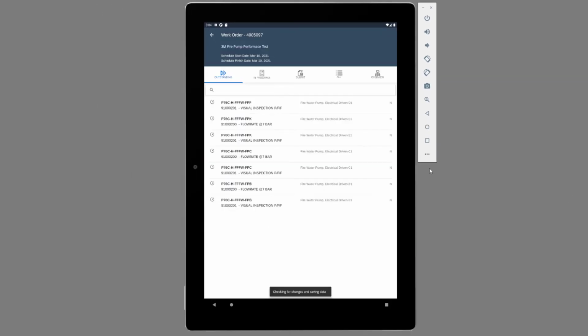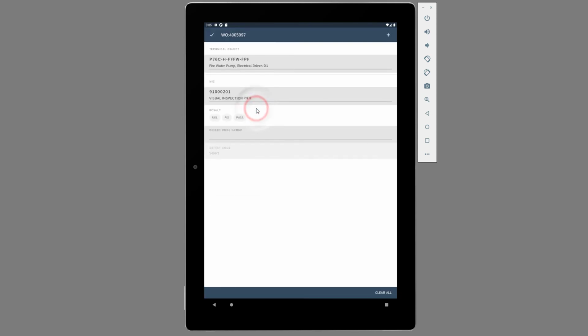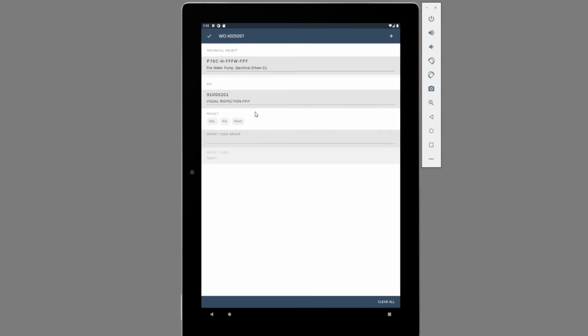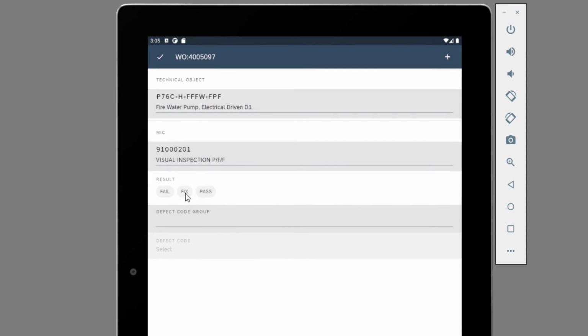However, the visual inspection, which is the second, takes a different turn. The initial condition, or as commonly known as found state, is not acceptable, but John tweaks few things as per the work instructions to bring the fire pump to an acceptable order. This means as left condition is acceptable. This, by the way, is a common routine performed by technicians during inspections.